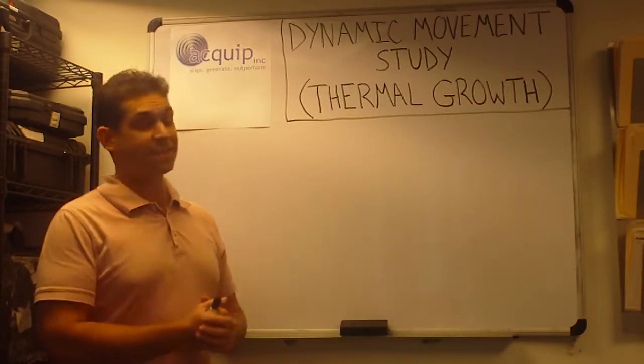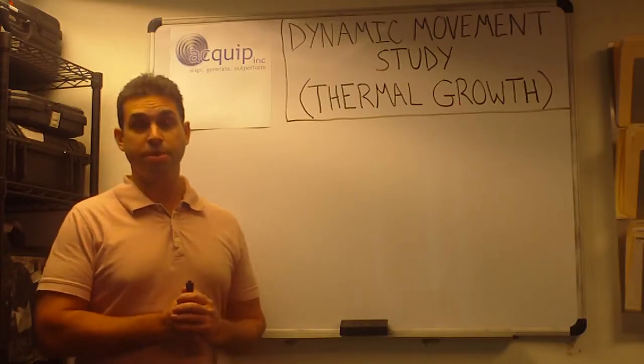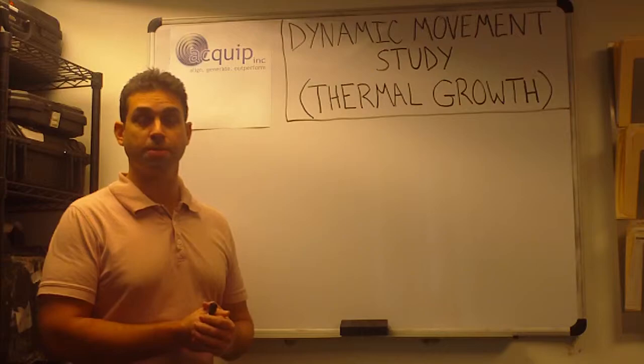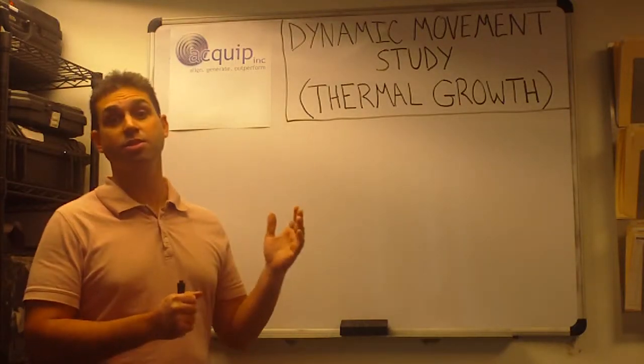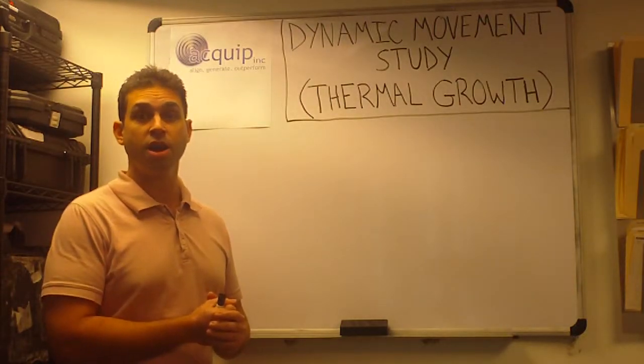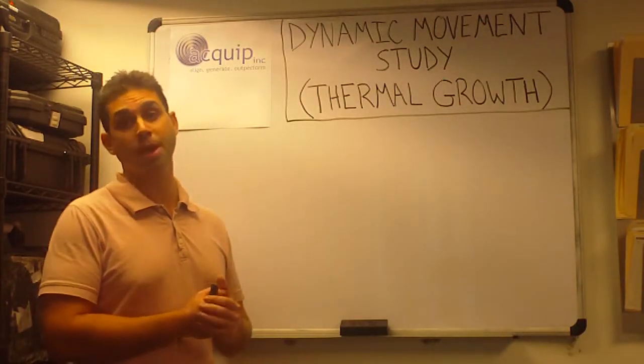First of all, thermal growth monitoring is a bit of a misnomer because it only ascribes machine movement to thermal growth. Actually, a lot of what's thought to be thermal growth is due to torsional movement of the machine and also piping strain.